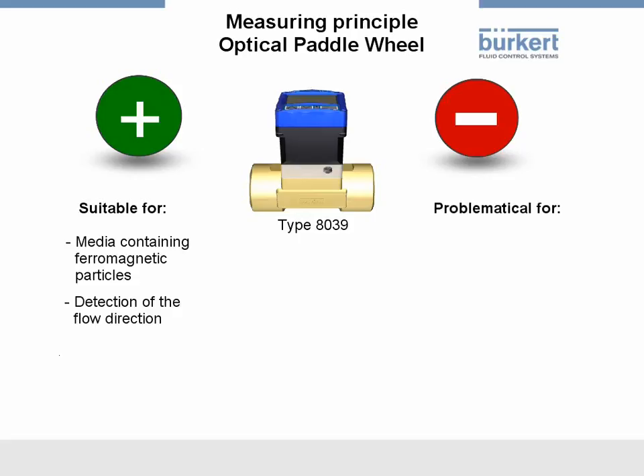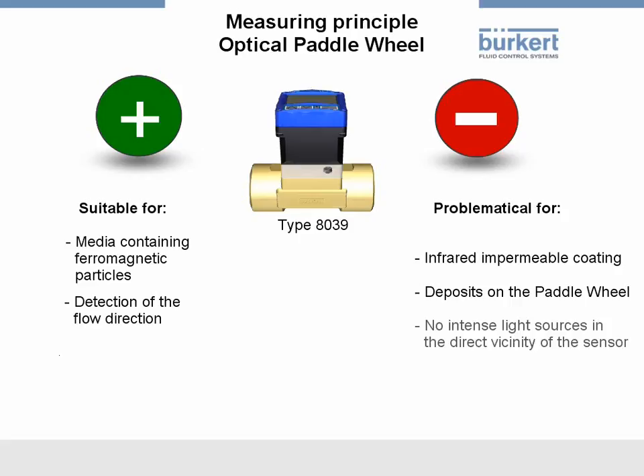However, this method cannot be used for fluids that can form an infrared impermeable coating. Also, deposits on the paddle wheel should be avoided because this can have a severe effect on the reflection behavior. Another important factor in the use of infrared signal acquisition is not to have any intense light sources in the direct vicinity of the sensor, since that can interfere with or completely prevent the detection of the reflected infrared signals.